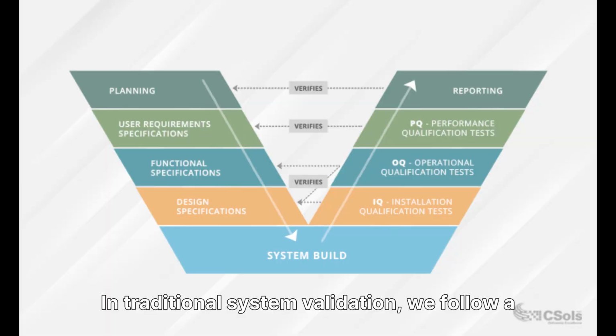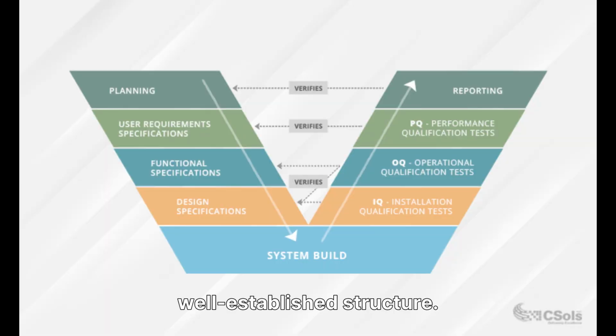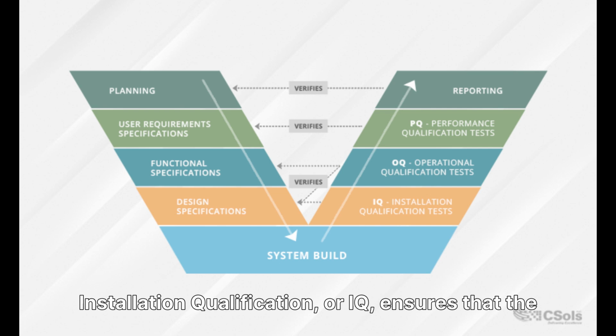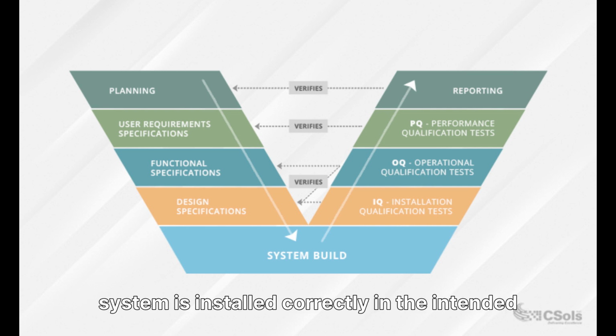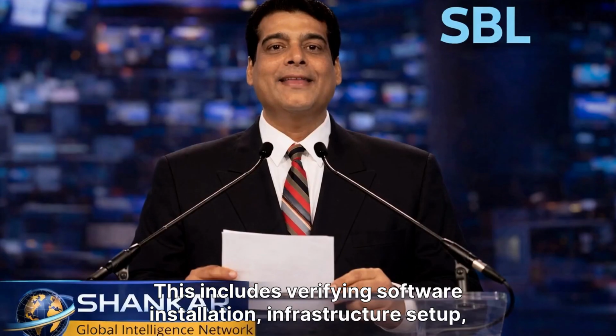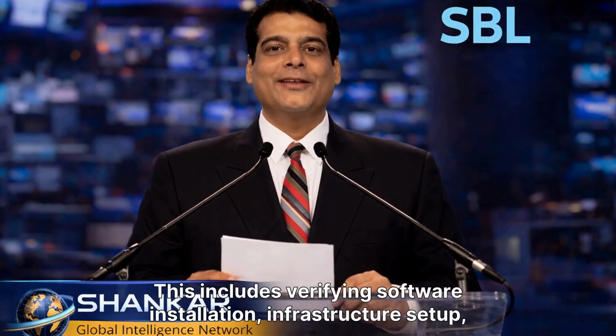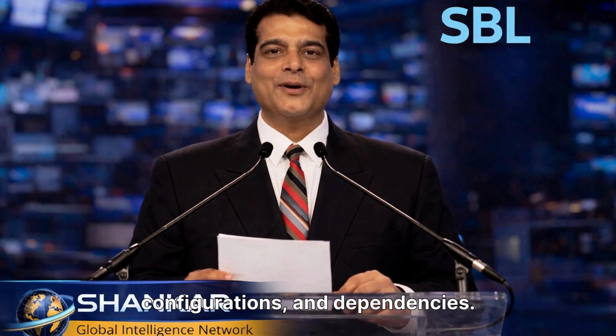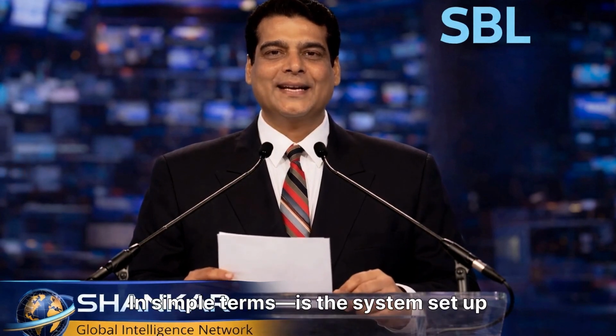In traditional system validation, we follow a well-established structure. Installation qualification, or IQ, ensures that the system is installed correctly in the intended environment. This includes verifying software installation, infrastructure setup, configurations, and dependencies. In simple terms, is the system set up correctly?